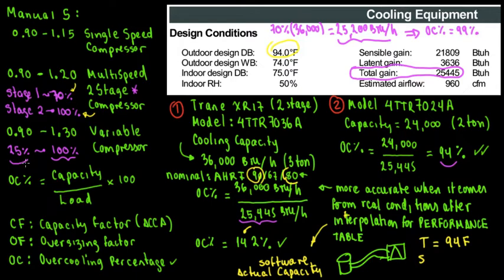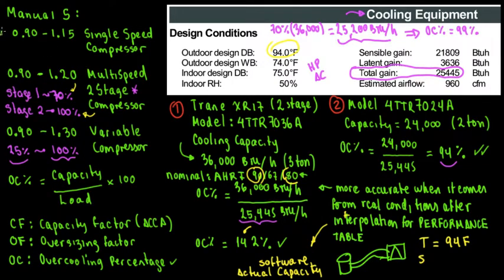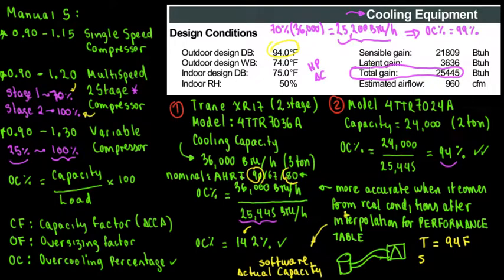The last part of this video: this is for AC only. But what about a heat pump? For a heat pump, you have to size the outdoor unit based on cooling only — you do not size it based on heating. All of these Manual S limits — limit one for single stage, limit two for two-stage, limit three for variable compressor — are going to apply. Size your heat pump based on cooling. In some future videos we're going to be talking about how to do the heat load calculation. I hope you enjoyed this video. Please hit the like button and subscribe. Thanks so much.